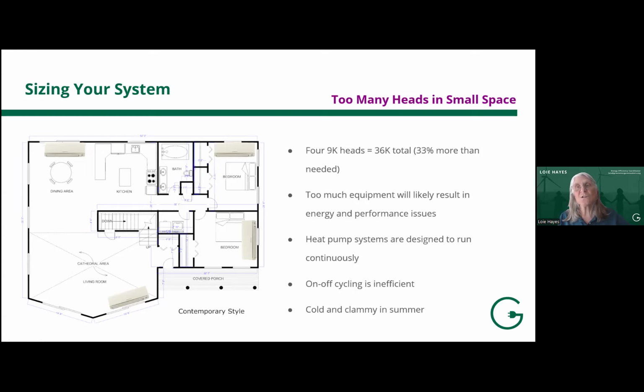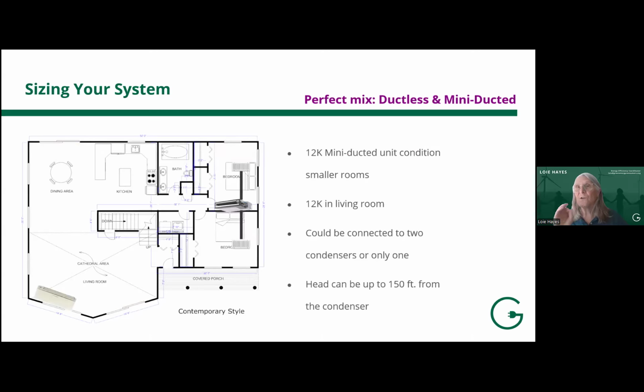And also in the summer, you could have a comfort problem because the dehumidification takes longer than the cooling. These bedrooms would get cool very quickly. The systems would shut off, but they would still be clammy because the dehumidification process didn't complete. So you want to really avoid oversizing. And to do that, you want to get a good heat load calculation, or at least a strong heat load estimate that you feel confident in.